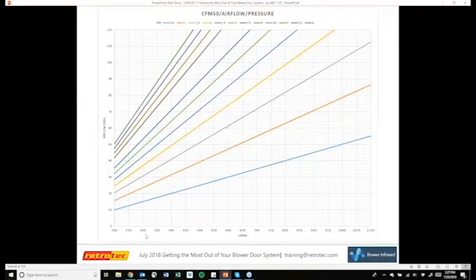Basically how this works is, on this x-axis at the bottom, this is going to be your blower door number, the number you're already going to know. On this y-axis is the airflow of the ventilation system. The way the two meet, what's important up here at the top is this key, and this is in pascals. These increments are the pressure difference between just the air handler fan running by itself and the air handler fan running with ventilation on.